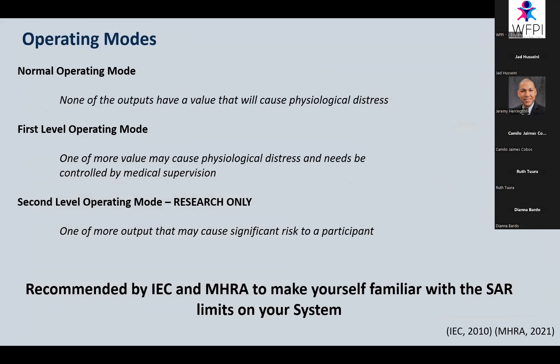Regarding operating modes: normal operating mode is where no outputs cause physiological distress — most scanning should happen here. First level operating mode is where one or more values may cause physiological distress and requires medical supervision, with the department defining what 'medical supervision' means. Second level operating mode is for research only, requiring ethics approval and written confirmation from the manufacturer, used where one or more outputs may cause significant risk to a participant.